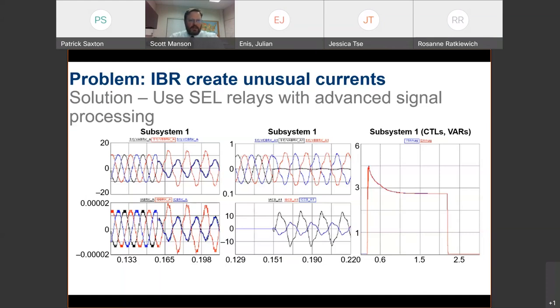Here's an example. You see what we call strong alpha components that make no sense to a protection engineer. A protection engineer would look at this event and scratch his head and say, wait, this can't possibly be true. But it is, because an inverter can do some pretty strange things. And the way that we get around them is using a protective relay with very advanced signal data processing to decode them and tell the customer, well, that inverter's okay, that one isn't. And by the way, this is the control strategy you can use to fix the problem you're seeing.